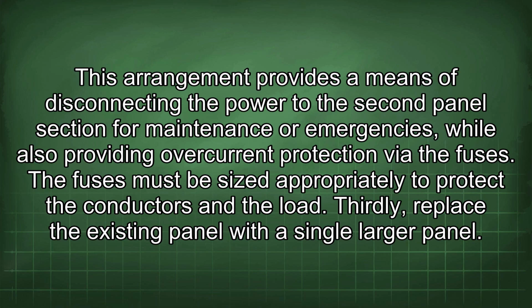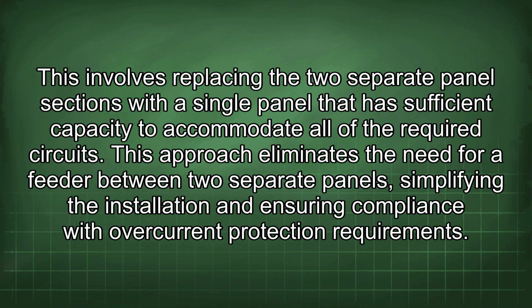Thirdly, replace the existing panel with a single larger panel. This involves replacing the two separate panel sections with a single panel that has sufficient capacity to accommodate all of the required circuits. This approach eliminates the need for a feeder between two separate panels, simplifying the installation and ensuring compliance with overcurrent protection requirements.